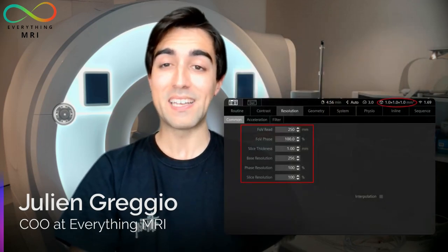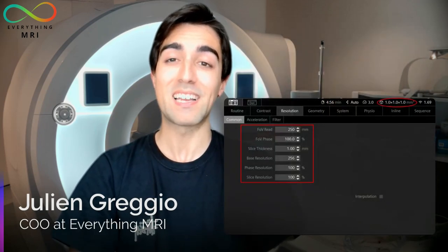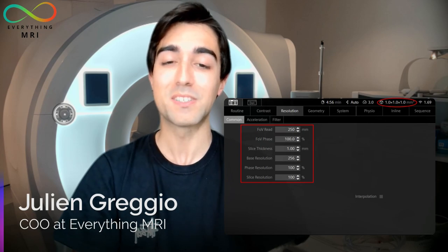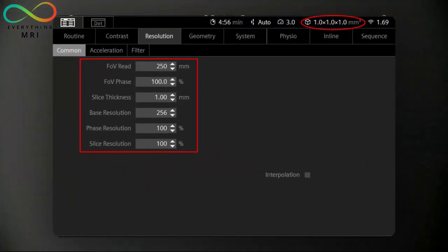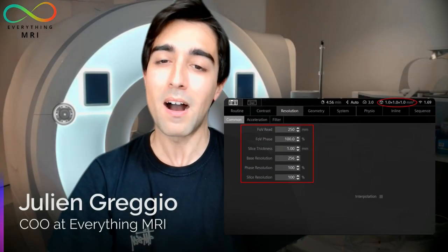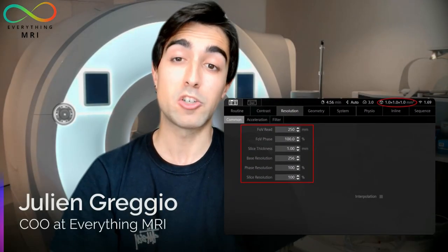Along with all these tips related to specific metal artifact reduction techniques, it must also be said that altering more common or routine parameters like voxel size might have a certain impact on the number of metal artifacts encountered. In fact, increasing the image resolution can be beneficial not only to reduce in-plane distortion but also to limit intravoxel dephasing — so it is worth keeping this in mind from an optimization perspective.